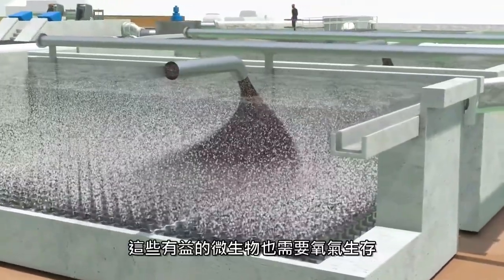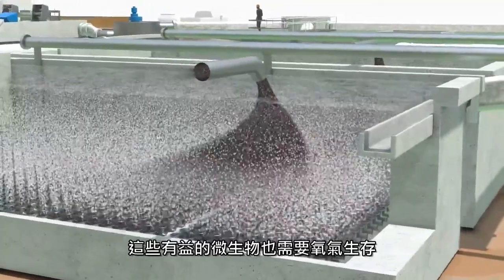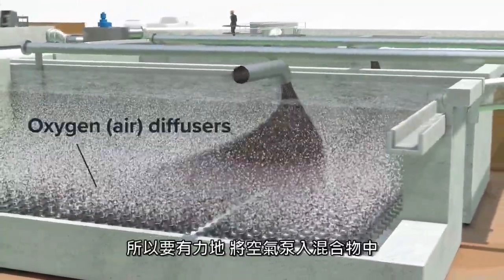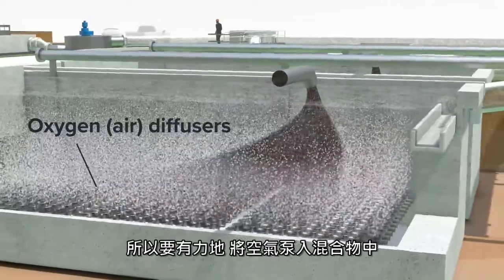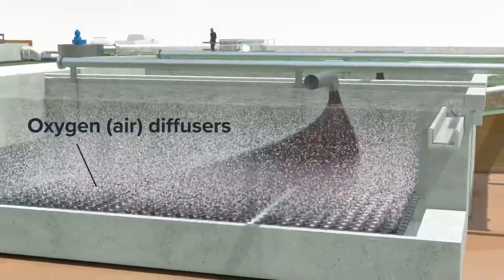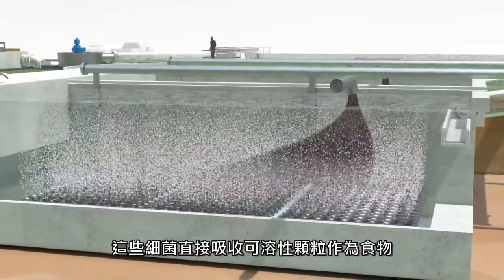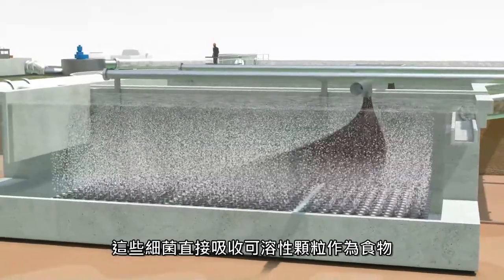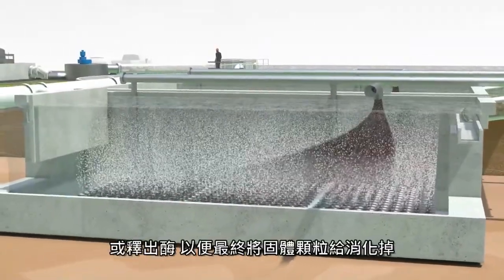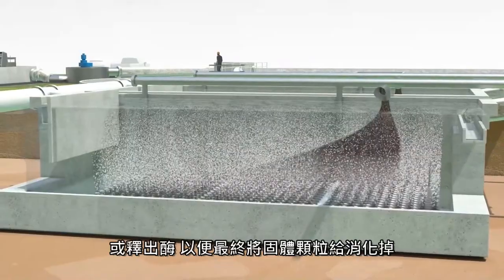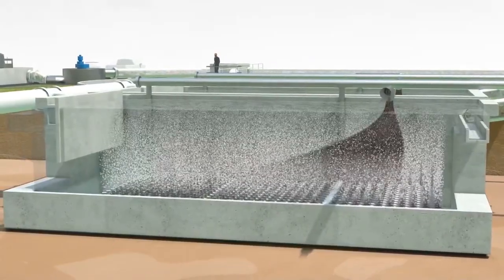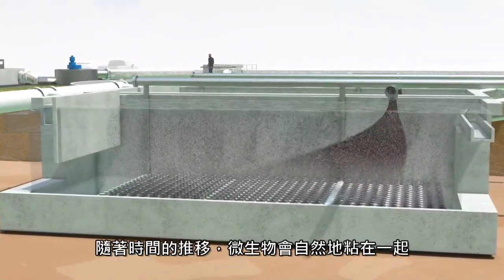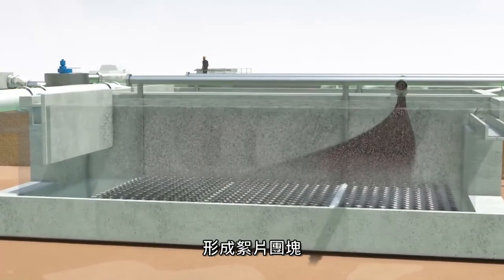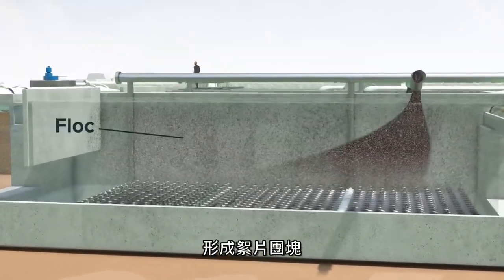These helpful microorganisms also need oxygen to live, so air is vigorously pumped through the mixture. These bacteria directly absorb soluble particles as food or emit enzymes that eventually allow solid particles to be digested. The microorganisms naturally stick together over time, forming clumps called floc.